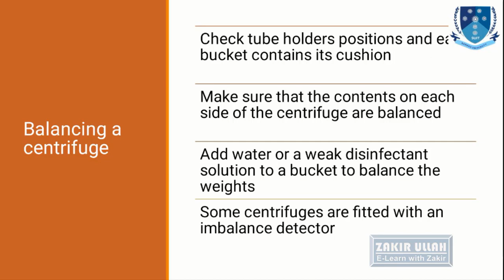So balancing is an important step in centrifugation. If we do not put a proper balance in a centrifuge, then some centrifuges will start alarming, or they will not start the process, because there is a detector inside the centrifuge called an imbalance detector. This type of detector does not allow the centrifuge to start when there is an imbalance, or when the centrifuge starts and detects an imbalance, it stops itself and the process is stopped.